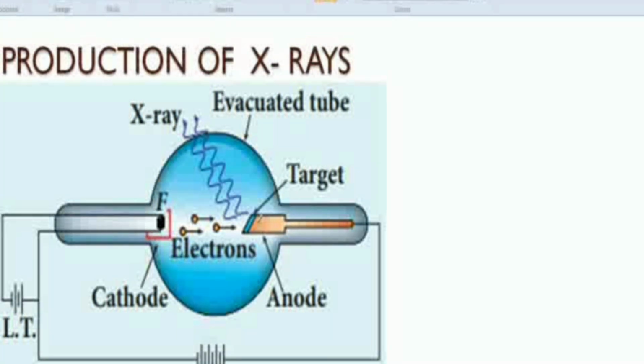That heat energy is absorbed by the copper metal. That's why the molybdenum or tungsten metal is embedded inside the copper, like a pot. The copper is used here because it is a highly conductive material. The cooling system is connected to the copper, so we can decrease the temperature of the material, right? So it's called the production of X-ray.